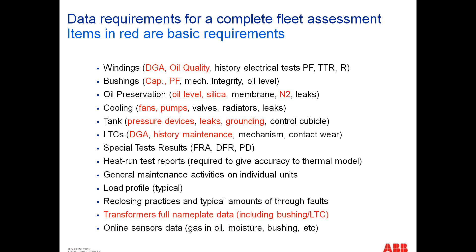And so what we want to do is have a condition evaluation program that's design-based. It considers the oil preservation system. It considers the materials in the transformer. We're seeing transformers today. We always used to assume they were copper with paper wrapped around the copper. We're seeing transformers today made with copper with an enamel on the copper. And so the breakdown characteristic and even the oil samples that you analyze will be completely different chemistry. So you have to know what chemistry, what are the materials inside your transformer that are breaking down as you use your transformer, go through the life of your transformer, and by understanding those materials, you're able to understand really what the condition of the power transformer is.